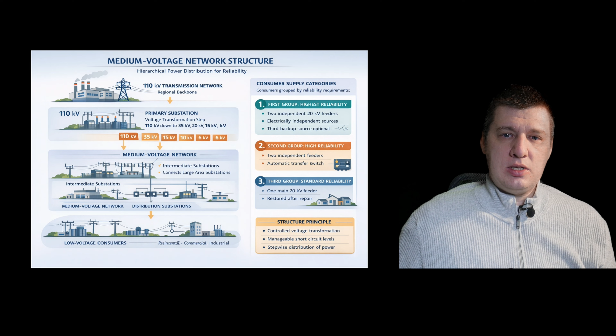The 35 kV level often acts as an intermediate level. It connects large area substations and distributes power further to the medium voltage feeders. The medium voltage networks then distribute power to intermediate substations and so on, distribution substations. From distribution substations, voltage is stepped down to lower voltage for final consumers. This layered structure ensures controlled voltage transformation, manageable short circuit levels, and stepwise distribution of the power.